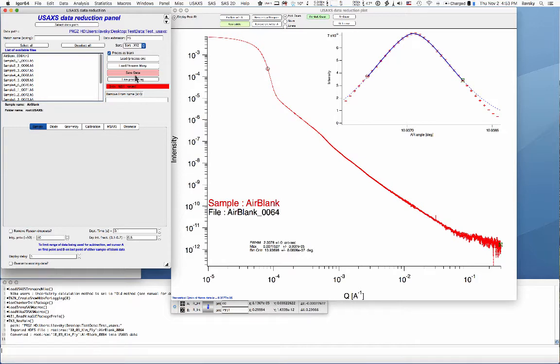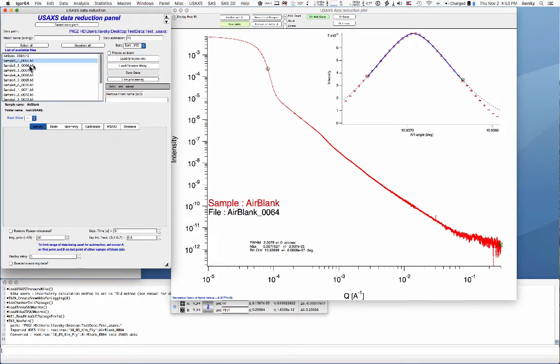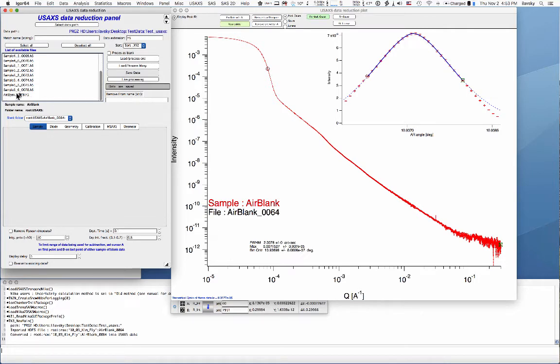Notice that the Save button is red, indicating unsaved data. Saving creates a proper copy of the data inside the Igor experiment. Once we have a blank, we can uncheck the blank checkbox, pick a sample, and assign the blank to it. I suggest measuring more blanks — here is a second blank which in this case looked identical to the first. If the instrument curve changes due to some drift or accident, having multiple blanks lets you pick the one most resembling conditions during your measurement. Select the sample, confirm the right blank, and process.